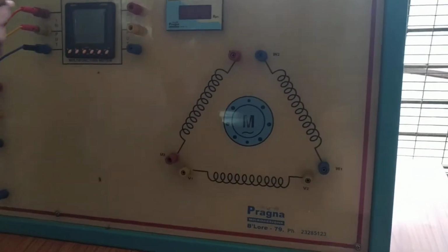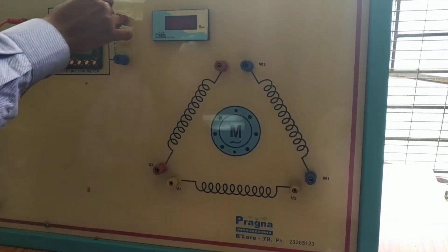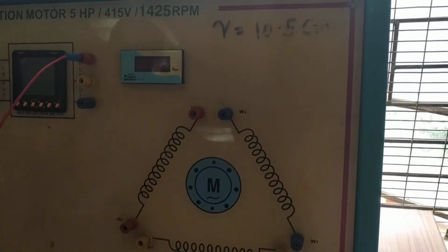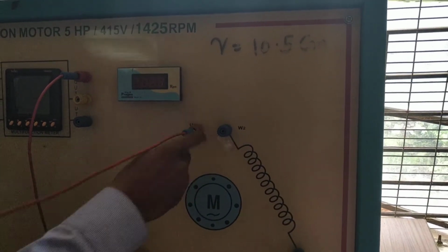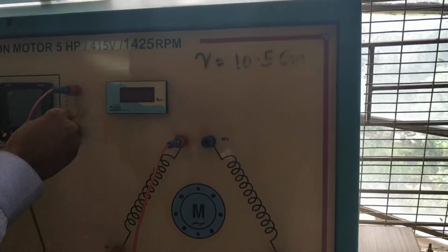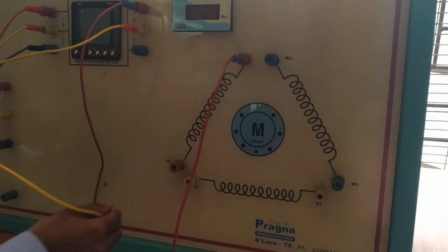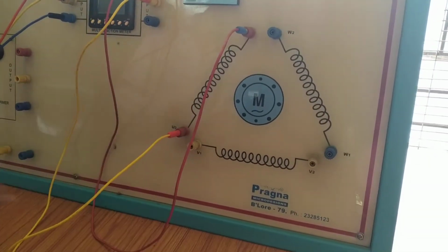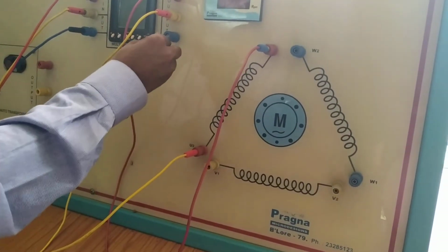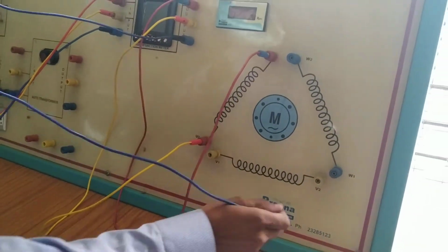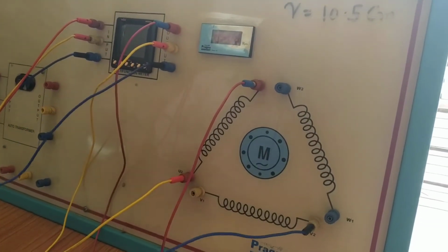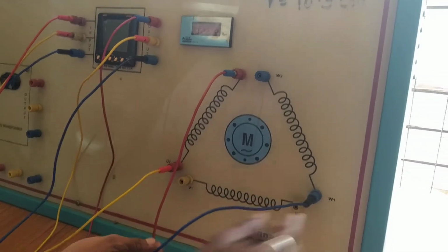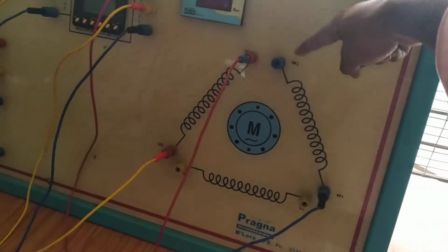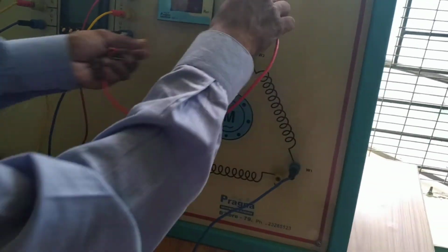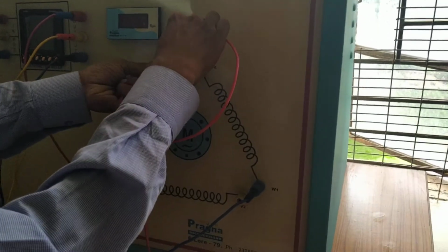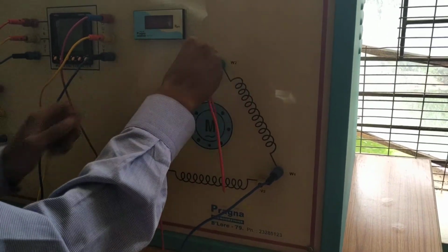Again, here we are using a delta connected 3-phase induction motor. R should be given to the first terminal, then the second terminal, Y phase, again B phase. So it is still not yet delta connected. To make it delta, all the terminals should be shorted here. Only then will it become a delta connected stator of a 3-phase induction motor.